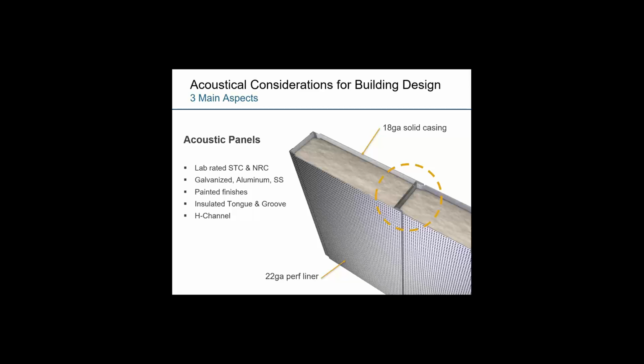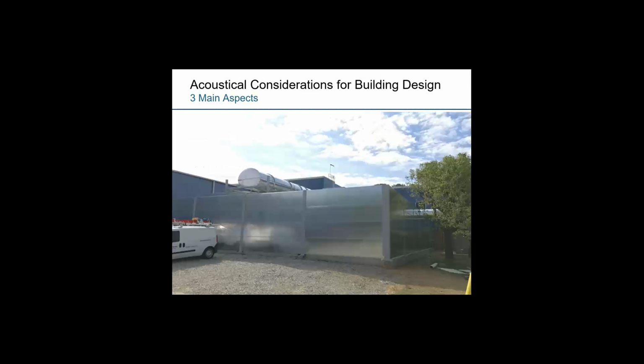Acoustic panels are another type of noise control product that work very well for blocking and absorbing sound energy. Silencers and sound attenuators work great for ducted applications, but acoustic panels are highly customizable for usage around things like radiated noise concerns, where you have maybe indoor or outdoor noise sources radiating into the environment or into another occupied space. An example of acoustic panels is something like this here, a traditional barrier wall of sorts that would be erected and installed around a noisy equipment, preventing direct line of sight to that equipment and blocking that noise radiating into the environment can greatly help with the overall reduction of sound energy.